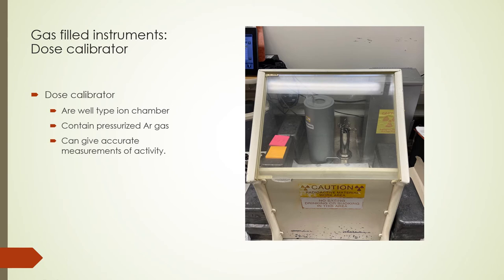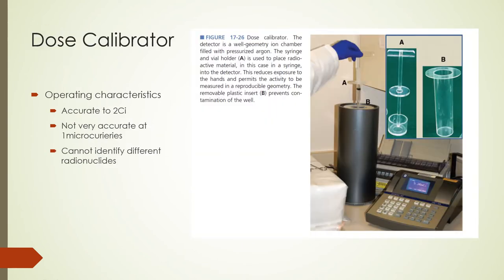Let's look at some examples of gas-filled instruments used in the nuclear medicine lab. The dose calibrator is a common instrument used in nuclear medicine. It is a well-type gas-filled detector that works on the ion chamber principle. It is filled with pressurized argon gas to increase its efficiency and can give accurate readings of radioactivity. The picture shows a dose calibrator behind leaded shielding. Dose calibrators are accurate to about two curies but are not accurate at low activities like one microcurie. There is a syringe holder and a vial holder to permit reproducible geometries, and a plastic insert to prevent contamination. Dose calibrators cannot be used as spectrometers because they cannot distinguish different radionuclides. Because they have large wells, they are not affected significantly by sample size or volume.